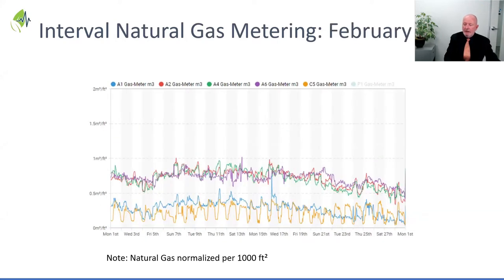So interval gas metering in the middle of winter, you see it there, the higher using hospitals getting up around 1 cubic meter per 1,000 square feet. The two most efficient being right in the middle, around 0.3 to 0.4 cubic meters of gas per 1,000 square feet. Again, very pronounced the difference. The seasonal variations are as interesting as the daily and the weekly variations.